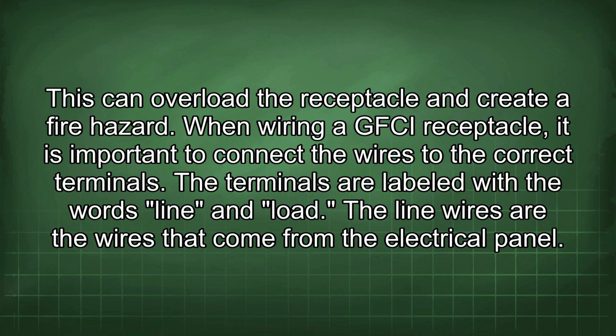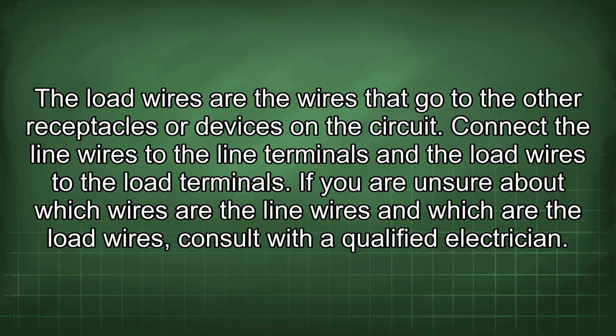When wiring a GFCI receptacle, it is important to connect the wires to the correct terminals. The terminals are labeled with the words line and load. The line wires are the wires that come from the electrical panel. The load wires are the wires that go to the other receptacles or devices on the circuit. Connect the line wires to the line terminals and the load wires to the load terminals. If you are unsure about which wires are the line wires and which are the load wires, consult with a qualified electrician.